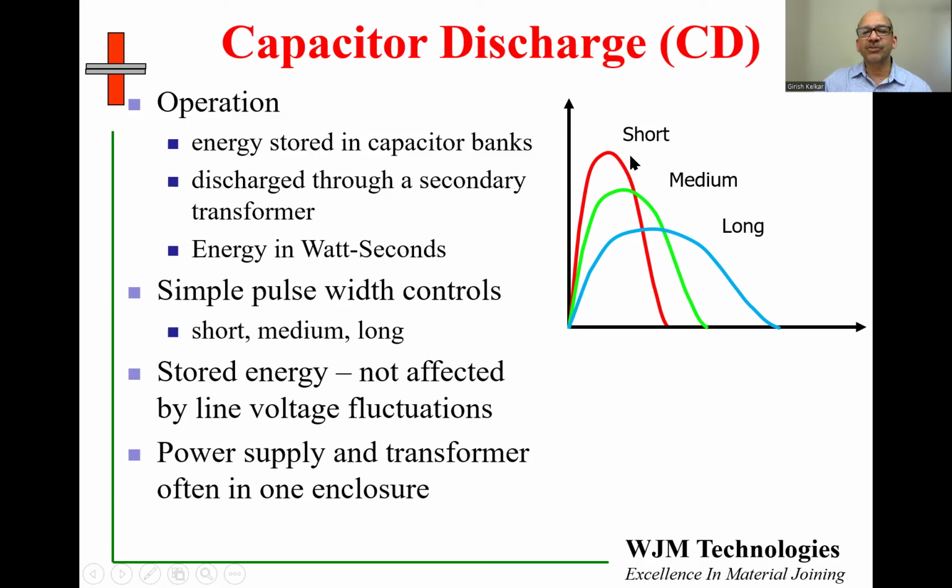The short for the small scale stuff typically is in the range of 2 to 3 milliseconds. Medium can be about 10 milliseconds, and long can be about 20 milliseconds. Again, every unit is slightly different, so best to measure and to check with the manual for that information.